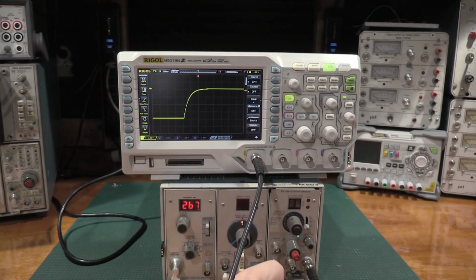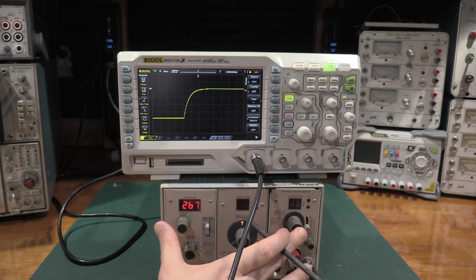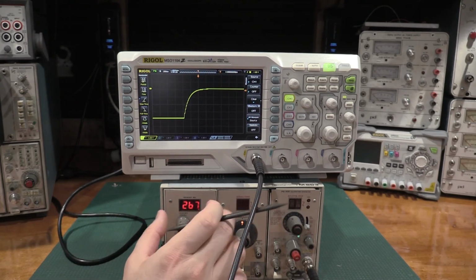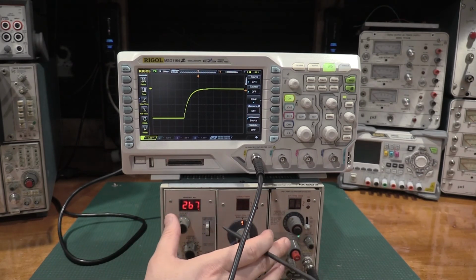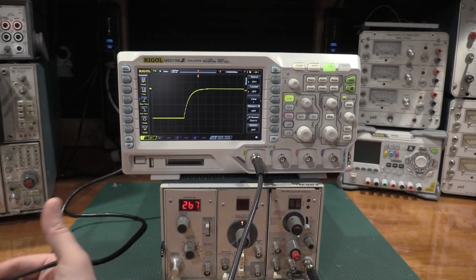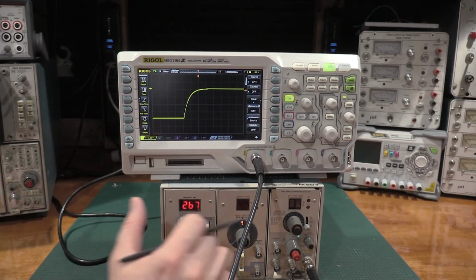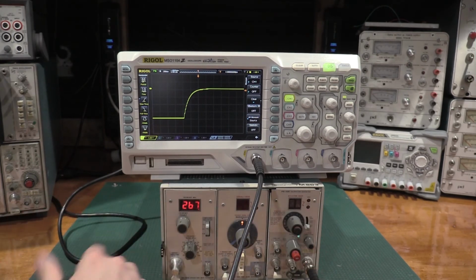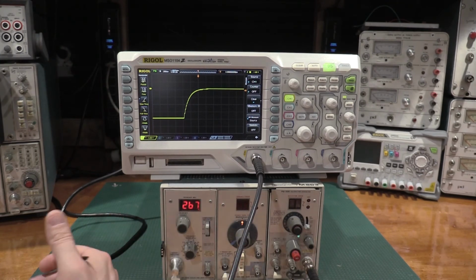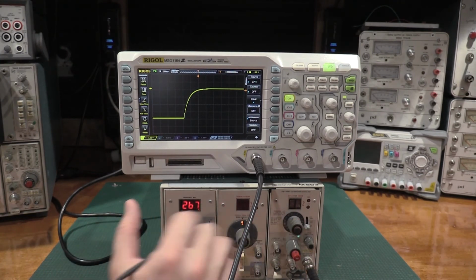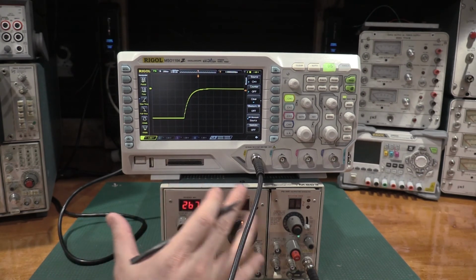The other thing we need is faster rise times. These 1 nanosecond rise and fall times down here are no longer sufficient. We need faster rise times to do the high frequency compensation in the vertical amplifier. Everything else is done here. Calibrating a scope does not need a ton of gear until you need to go fast. So if you're looking at a 5000 series, that's 10 megahertz, 50 megahertz, 75 megahertz, this is fine. 465, this is fine. Anything under a 465, this is fine. 500 series, this is great.